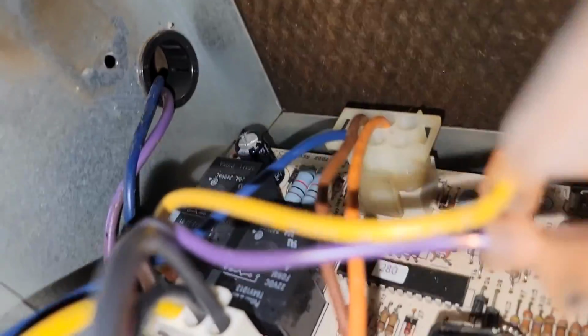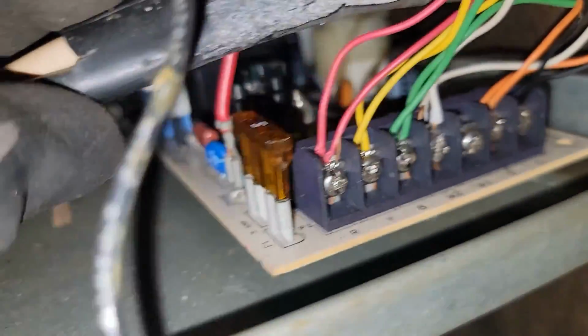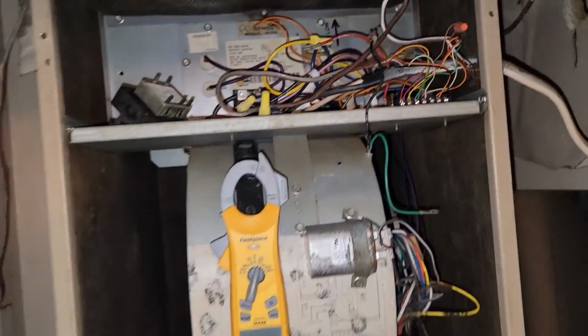Is the board burnt at all? It doesn't look like it. Fuse is not blown. Let me go outside and check the condenser. You have a bad transformer, that means there is a cause. Usually there is a cause. So what I'm doing is I'm trying to find the cause, because the effect was the transformer is now bad. Let me show you what I'm looking for.